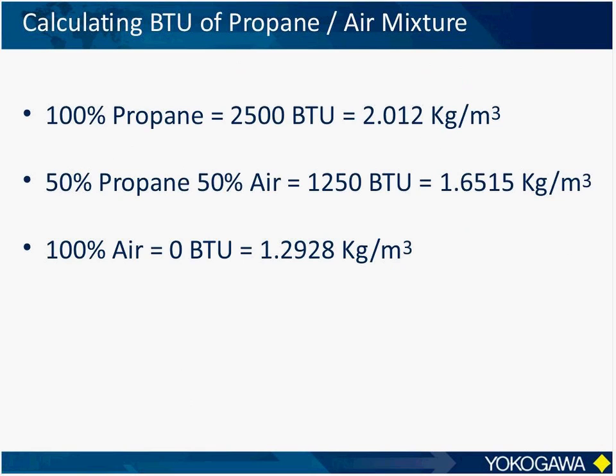So as with percent concentration calculations, we can use a simple calculation to calculate the BTU content of the binary gas stream based solely on the density measurement. We know the densities and the BTU contents of the 0 and span ranges of the binary gas stream, so we simply program these constants into the analyzer. The analyzer will then calculate the BTU content based on the measured density.